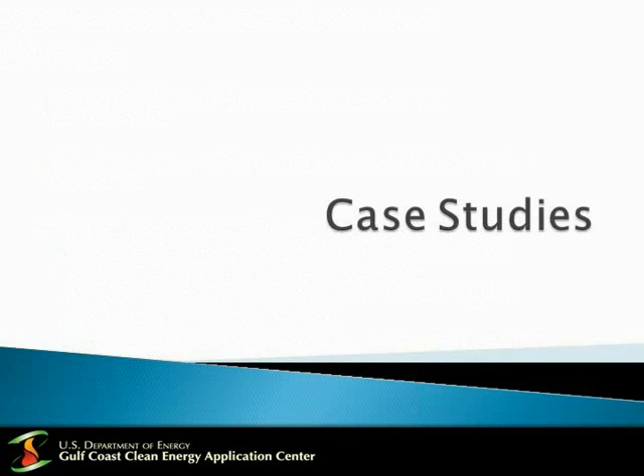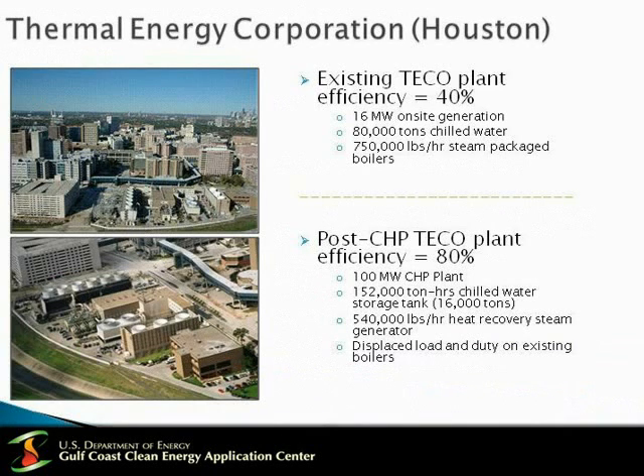Now, let's look at the recent Texas projects and also some case studies of CHP installations. This one is the Thermal Energy Corporation, TECO, which actually serves all the chill water and steam needs at the Texas Medical Center in Houston. The existing TECO plant efficiency was about 40%. At that time, it had 16 megawatts of on-site generation. You had 80,000 tons of chilled water, and you had 750,000 pounds per hour steam packaged boilers.